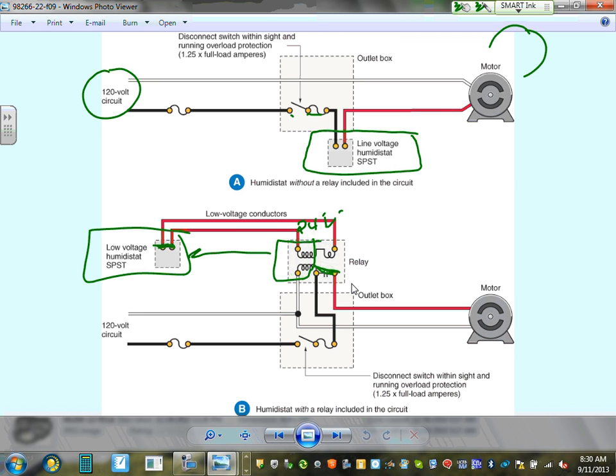That's a question you're going to be asking yourself every time you have mechanical equipment, such as a fan, pump, chiller, air handling unit, and so forth. So what you're looking at right here is controllers. This is a box, a device that has a disconnect as well as a controller and an overload, where you bring the power in and power out. And this is another box that interfaces with it that has a relay that's driven by a third box that has the thermostat or the humidistat. Thermostat based on temperature, humidistat based on humidity. Any comments, guys? Any questions? Does that make sense? Yes, no? No? Okay, so that's basically it.